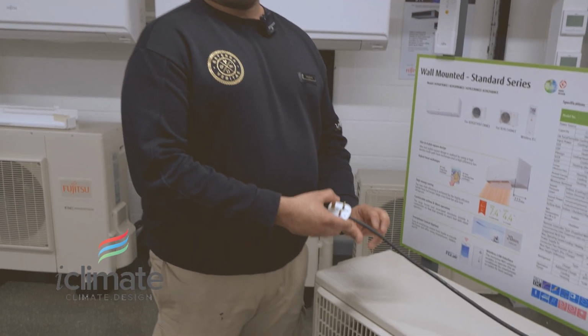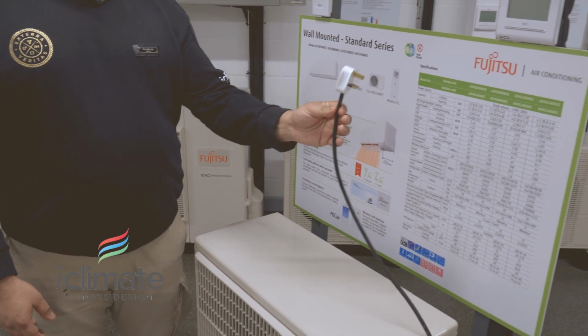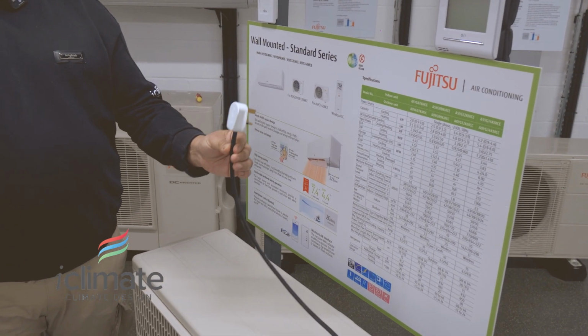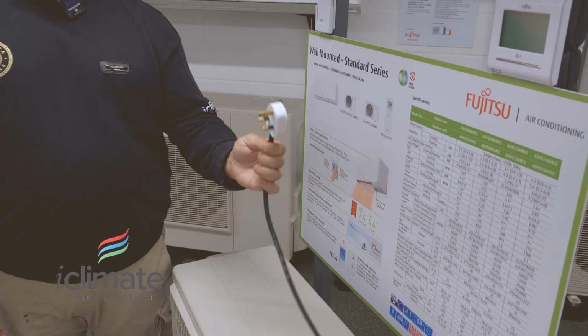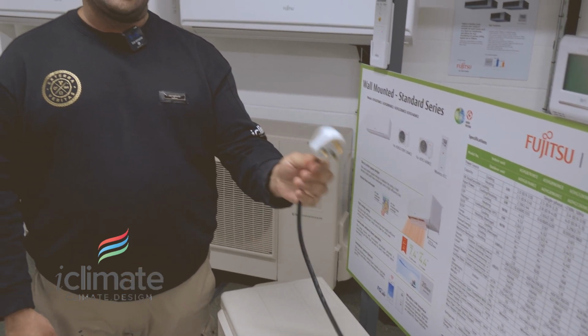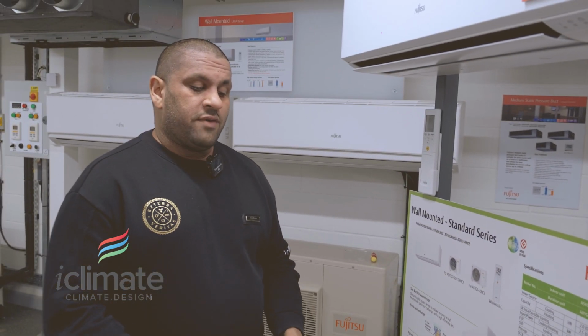Final question we get asked is, how do I power my air conditioning unit? As you can see, the majority of split type air conditioners going up to 4 kilowatts can essentially be powered off your 13 amp plug power supply. This can be off a plug, or if you don't wish to use a plug, you can have one of our electricians come in and use an independent power supply from the fuse board, or utilize the ring main running in your house currently, which we can drop down to a fuse spur, and then you can safely power your air conditioning system from it.